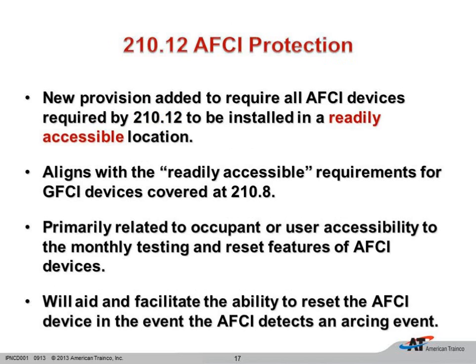210.12. So now we are in some AFCIs, arc fault circuit interrupters, and this section was completely redone. So we can see that AFCIs now also have to be readily accessible, and this is mostly a residential requirement with AFCIs. Where this has been completely redone, we'll take a look at this, because first of all, what they've done is they've expanded the rooms.